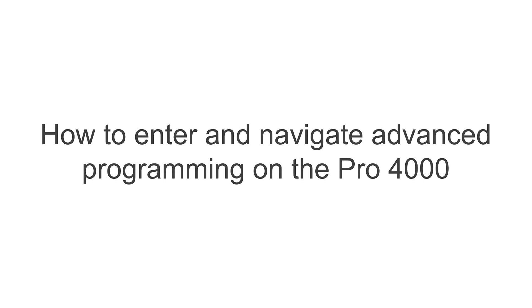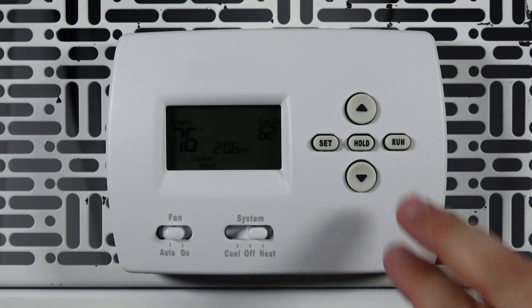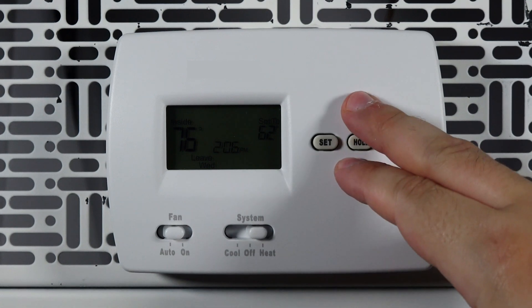Hi everyone. In this video I want to cover advanced programming for the PRO 4000 thermostat. To enter advanced programming, hold both arrow buttons together for 5 seconds.